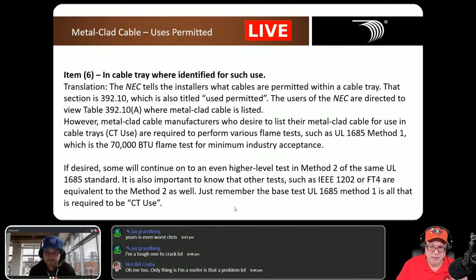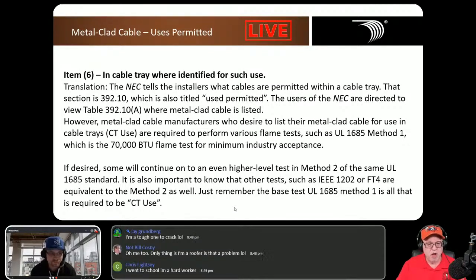Now, if you see something like IEEE 1202 or FT4, then you know it went to an even higher level. We have the minimum requirement with Method 1, and then a higher level, which is considered Method 2 of 1685, which is equivalent to IEEE 1202 or FT4. Incidentally, Jay, FT4 is a Canadian standard, but it's equivalent to the engineers' standard of 1202, which is equivalent to 1685 Method 2, in case y'all didn't know that. So if your MC cable has a tag that says it's okay for CT use, slap it in a cable tray, follow all the rules in 392, and you're good to go.